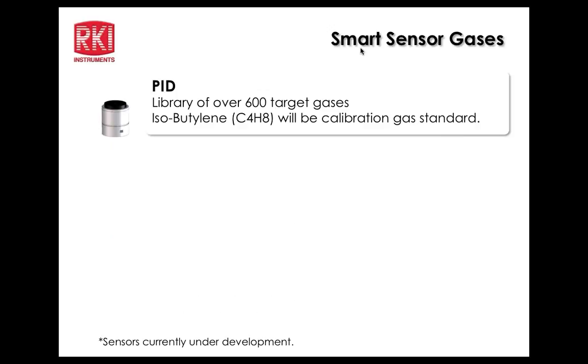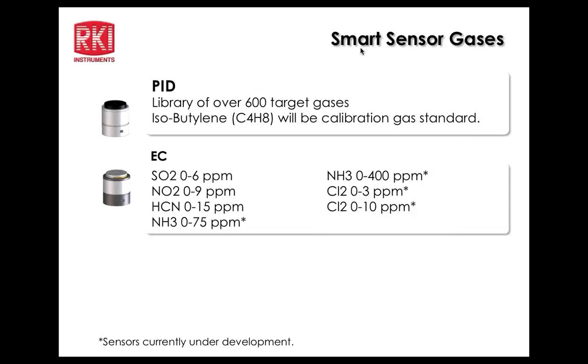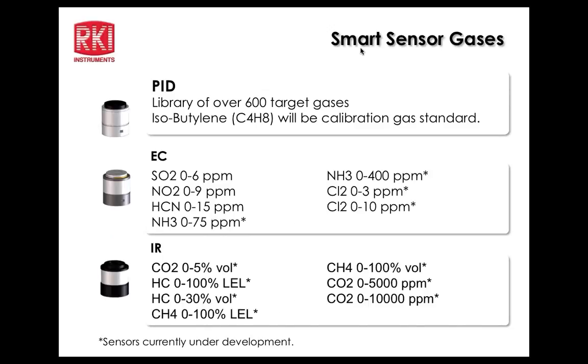We'll go ahead and continue on. The PID will have a standard calibration to isobutylene, the typical industry standard calibration gas. The electrochemical sensors will detect SO2 0 to 6 ppm, NO2 0 to 9, HCN 0 to 15, ammonia 0 to 75 and also 0 to 400 for a higher range, and chlorine at 2 scales, 0 to 3 and 0 to 10 ppm. The asterisks denote sensors currently under development, with availability around February. SO2, NO2, and HCN are currently available as electrochemical sensors.